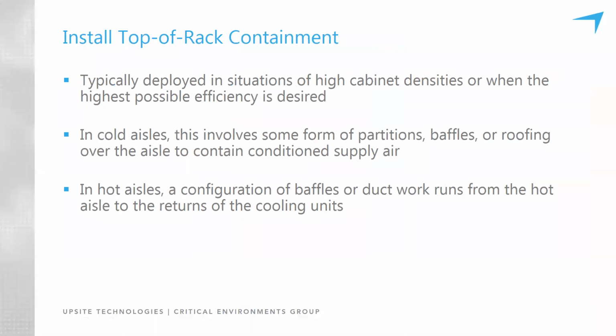Nice. So now that we've got doors on the end of the aisles, let's start looking at what we do above the row for containment. Typically, installing containment above the cabinets is done for higher density environments, but it's also potentially very important for other layouts in the room where there may be a low ceiling, and when the cooling units may be on opposing walls, causing the exhaust air from a hot aisle to flow over the top of a cold aisle to get back to the cooling units.